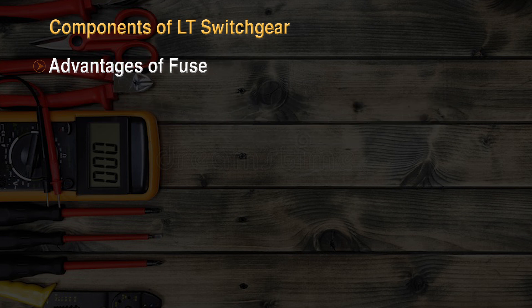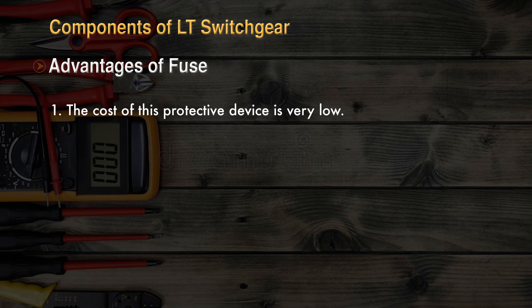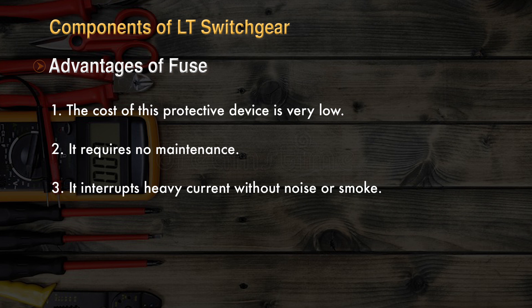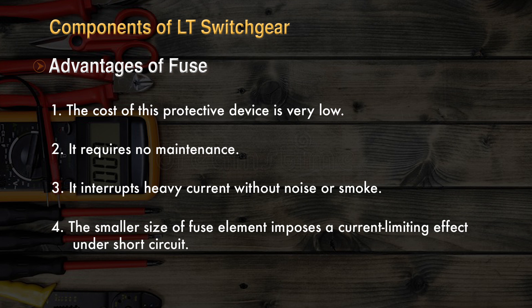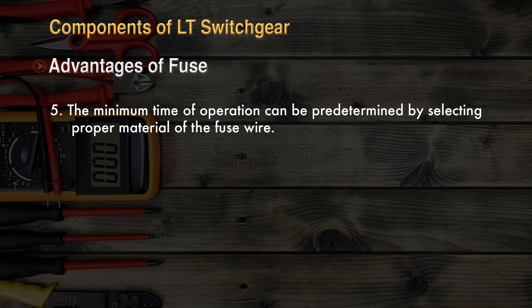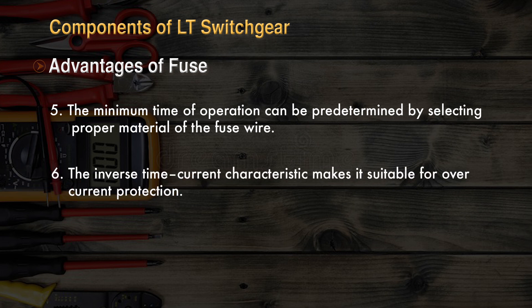The advantages of a fuse are: the cost of this protective device is very low; it requires no maintenance and interrupts heavy current without noise or smoke; the smaller size of the fuse element imposes a current-limiting effect under short circuit; the minimum time of operation can be predetermined by selecting proper material of the fuse wire; and the inverse time-current characteristic makes it suitable for overcurrent protection.